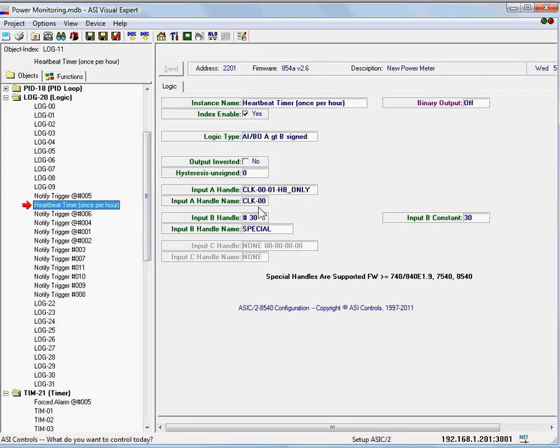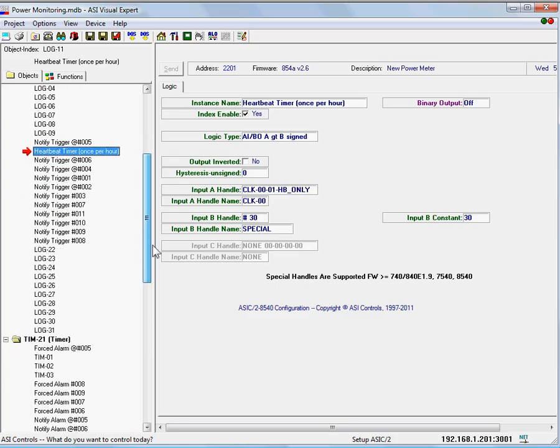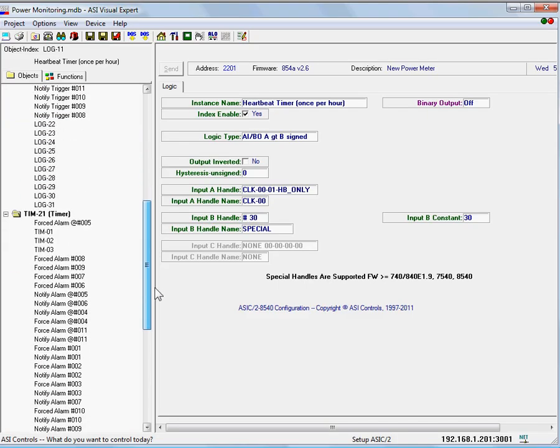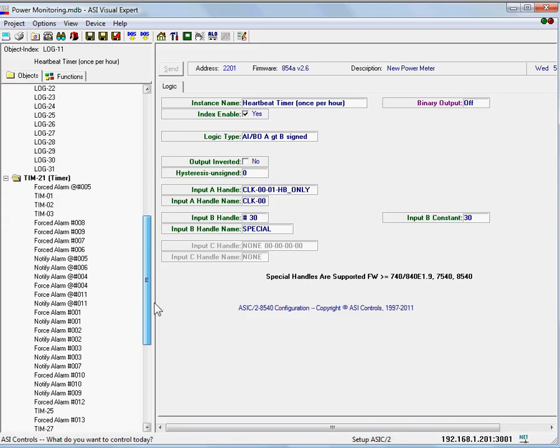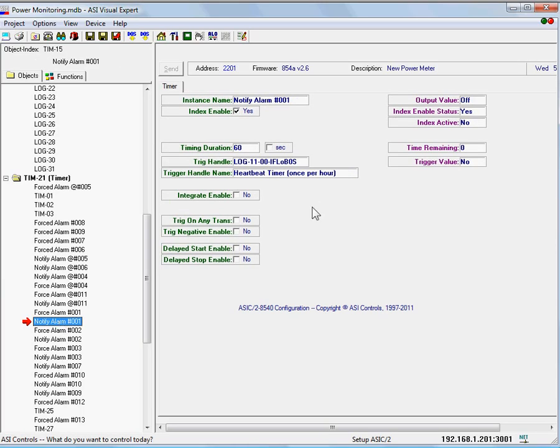We then have a couple timers that are attached to that, and we'll look for a particular site here. Alarm number one, the notify alarm number one, is triggered off that logic object, and it fires for 60 seconds when that logic object changes state.